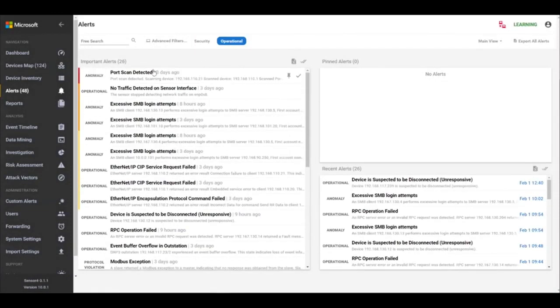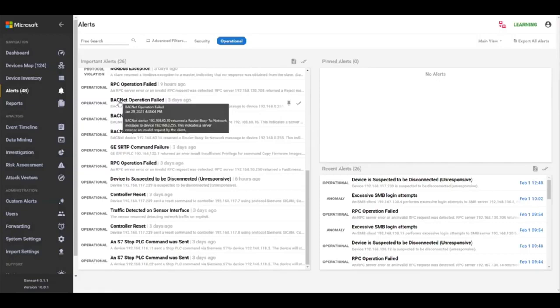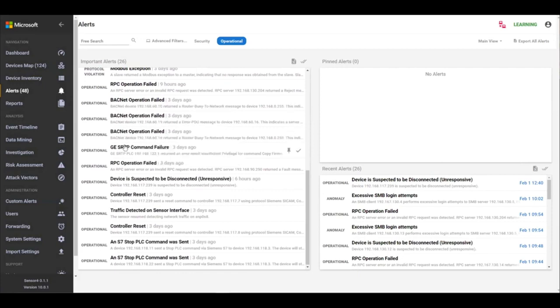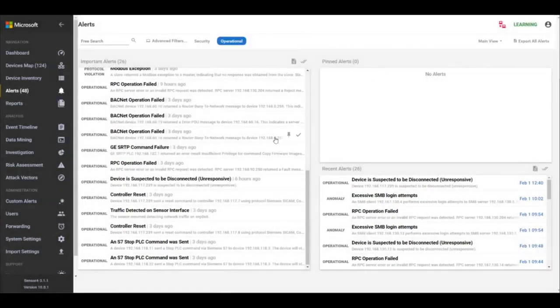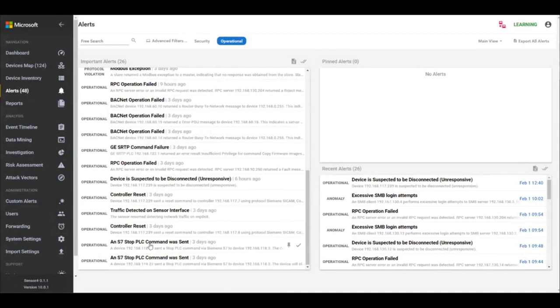And then if we go to the operational side, we can see port scans and SMB login attempts, things like that, as well as actual protocol type issues that may occur. So actual BACnet protocol operation failed, that's a cause for concern, maybe depending on what the situation is. And you can also see the stop PLC command was sent right here. So this is the example that was shown in the slide deck. All of this is giving you the view into not only are we understanding the packets between two individual devices, but we're looking inside of the actual commands inside of the actual packets to understand what is actually happening to these devices and alerting based on the actual deep packet inspection.